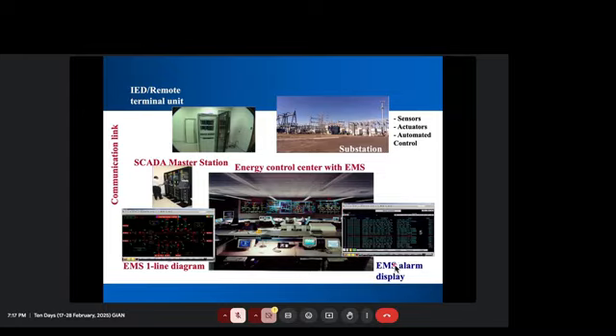So alarm is very important, because this is what we call attention span, which means the operator will respond to the alarm if it is controlled in a way that there is not alarm all the time. And if there is a lot of alarm, then it is already prioritized. So the software needs to do that alarm processing and prioritize it, then send it with different color or different priority to the operator. So now the operator will understand it better, that okay, this is critical, I need to take care of this.